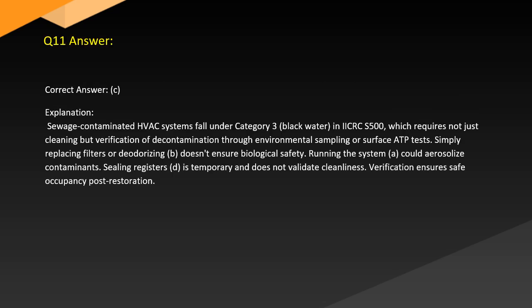Answer. Correct answer: C. Explanation. Sewage-contaminated HVAC systems fall under Category 3, black water, in IICRC S500, which requires not just cleaning but verification of decontamination through environmental sampling or surface ATP tests. Simply replacing filters or deodorizing, B, doesn't ensure biological safety. Running the system could aerosolize contaminants. Sealing registers, D, is temporary and does not validate cleanliness. Verification ensures safe occupancy post-restoration.